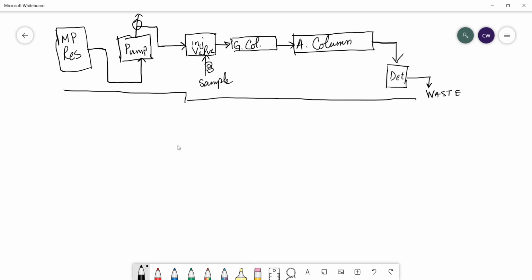There we go. Okay. So those are our two major considerations for our mobile phase and its reservoirs. Now, some instrument manufacturers will actually take a multi-layered approach, which is really good, and they will have degassing built right into their mobile phase reservoir controllers. I know Dionex, which is now Thermo, does this. They have online helium sparging built into the mobile phase reservoir platform, and then you keep your eluents under pressure, and they also recommend that you offline degas it before you even put them in, so that there is near zero gas contamination in your mobile phase.